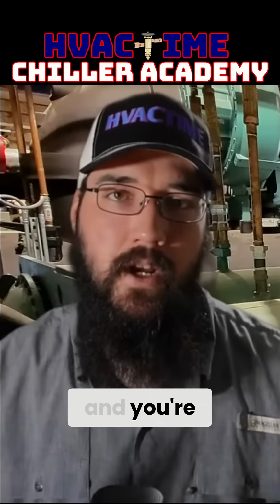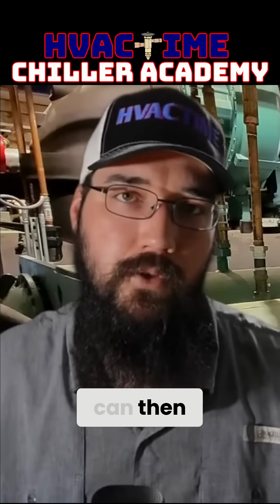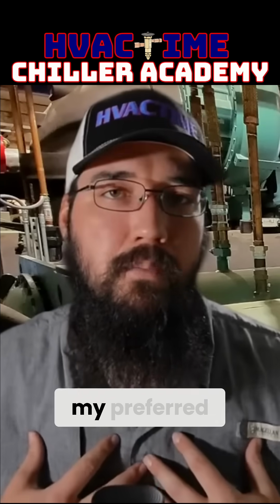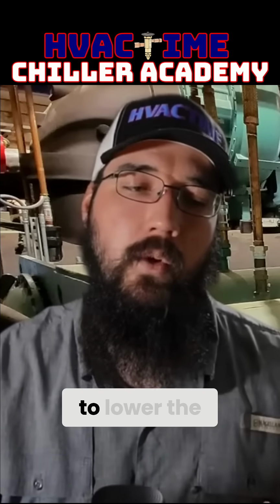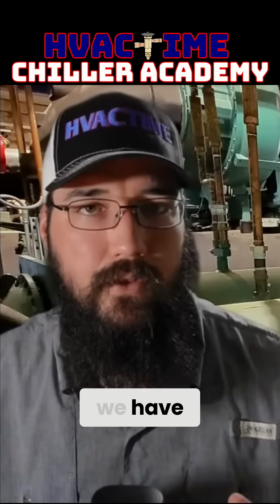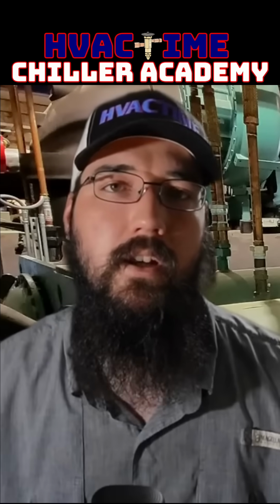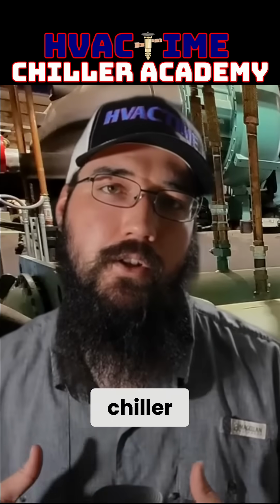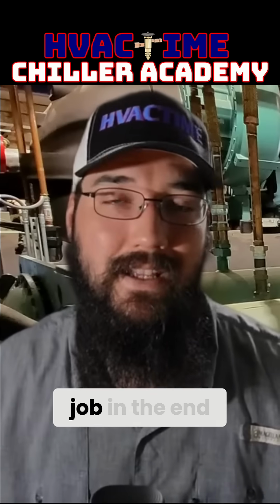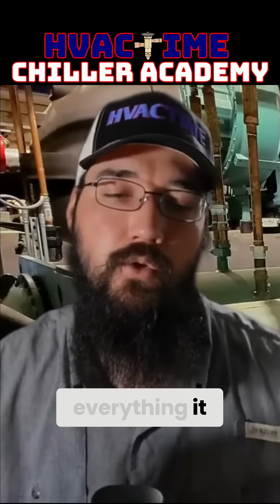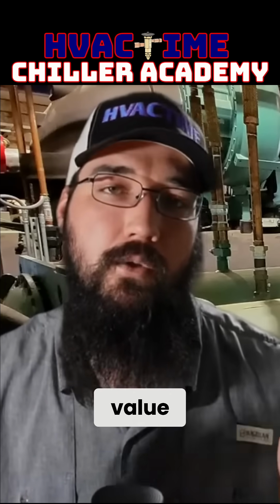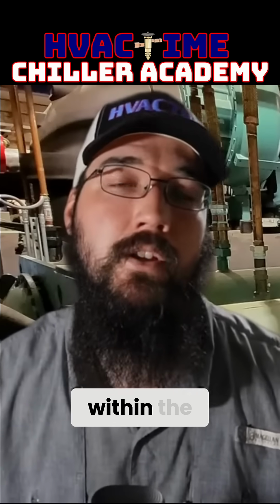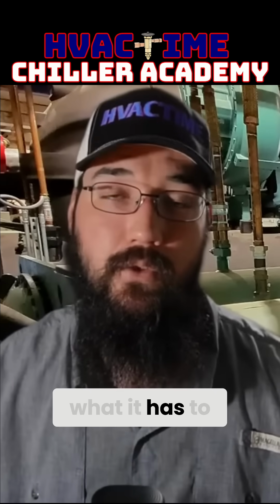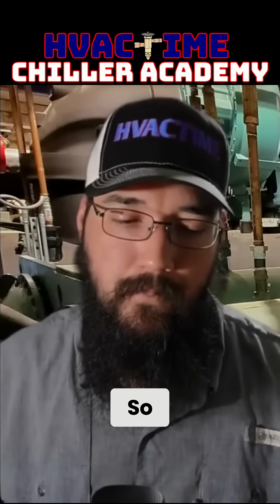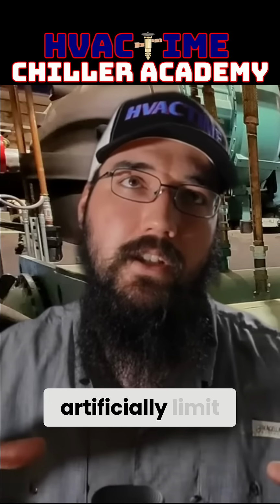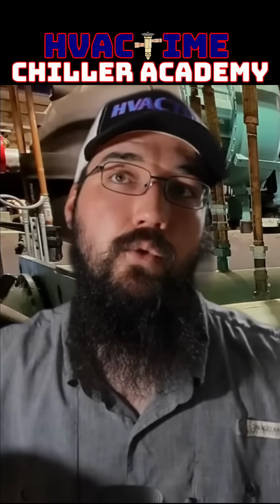If you have a surge condition and you're trying to get the chiller out of a surge so that you can then further troubleshoot, there are two methods. My preferred, my ultimate preferred method is to lower the current limit, because what we have to do is get our lift under control. The chiller is doing its best to make set point - that's a chiller's job in the end. The controls package is doing everything it can to that machine in order to achieve the set point value it's been given, period. It's going to try to do that within the safety parameters as best it can. It's going to do what it has to, and sometimes that means it pushes these boundaries. So by lowering the current limit, we can artificially limit how much the compressor is allowed to ramp.